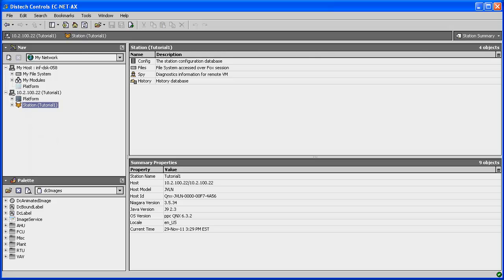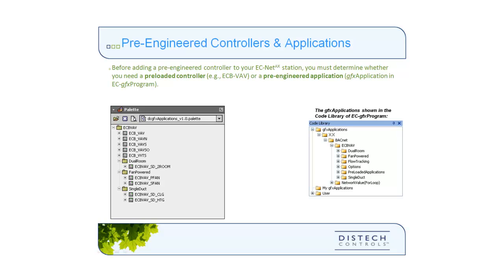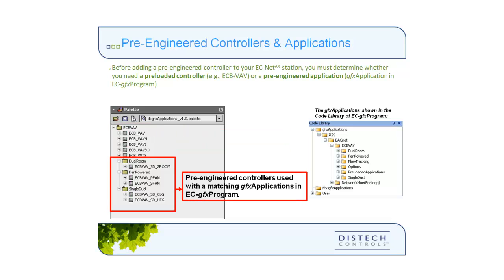Now we will move on to adding pre-engineered controllers to an ECNet-AX station. Before adding pre-engineered controllers, you must determine whether you need a pre-loaded controller or a pre-engineered application. The DC GFX Applications palette contains these pre-engineered controllers. The first part of the list consists of pre-engineered controllers used with pre-loaded controllers — drag and drop one to obtain a working device complete with code and graphics in minutes. The second part consists of pre-engineered controllers used with GFX Applications, which contain a complete library of pre-engineered sequences embedded within ECGFX Program and must be downloaded into the controller using the synchronized feature.